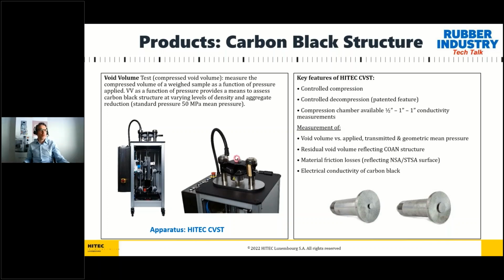The key features of our void volume tester are controlled compression and controlled decompression. This is a feature that HITEC has patented. We have a compression chamber available in half inch, 1 inch, and a special 1 inch for conductivity measurements of carbon black.